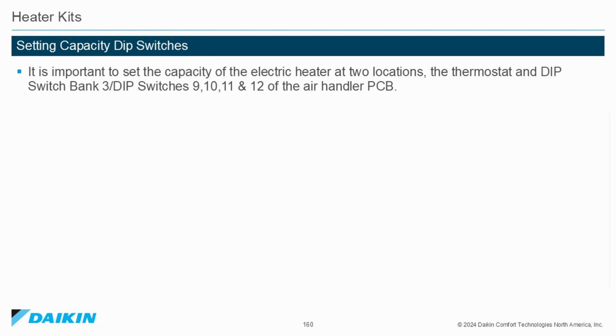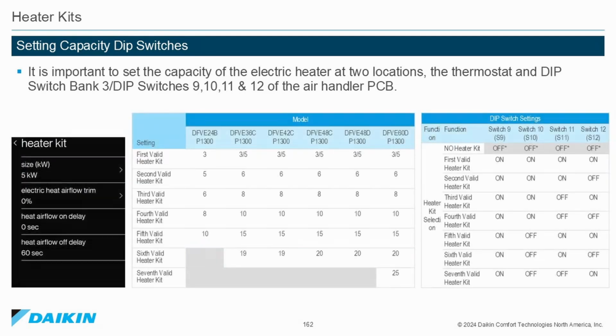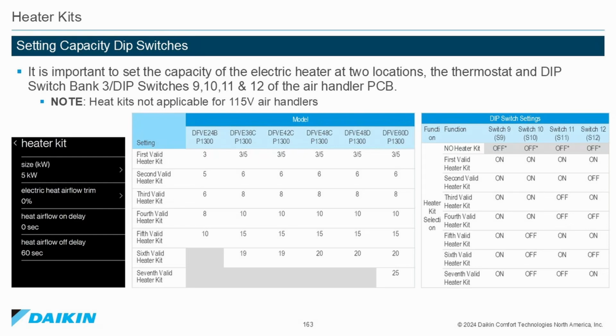Setting capacity dip switches. It is important to set the capacity of the electric heater at two locations, the thermostat and the dip switch bank 3, dip switches 9, 10, 11, and 12 on the air handler printed circuit board. Note: heater kits are not available for 115-volt air handlers.